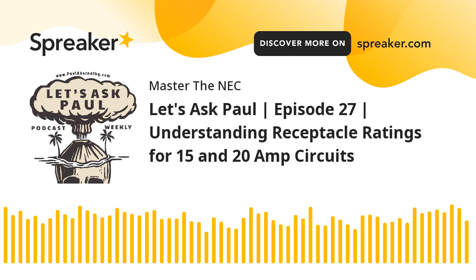And then I'll remind you again at the end, if it was a 20 amp rated circuit breaker, I can put a 15 amp duplex on it. I just cannot use a 15 amp simplex on that 20 amp branch circuit. You with me? Hopefully that is crystal clear. But the key is reading the language in 210.21(B)(1) to understand. And we do this all the time for these applications. Sometimes you just don't think about it, but we do. Okay, that's pretty much all I wanted to cover for that episode.